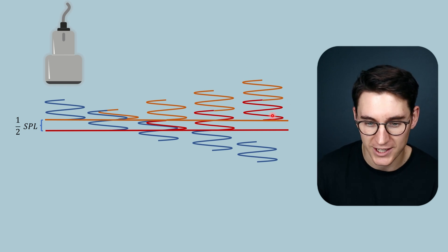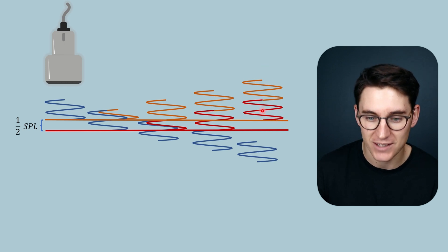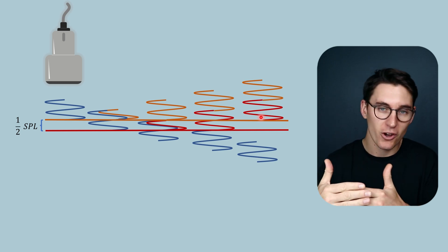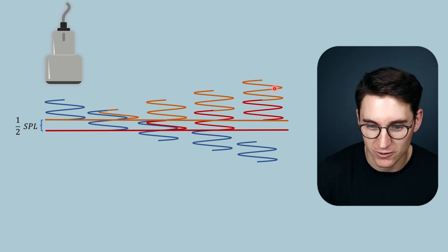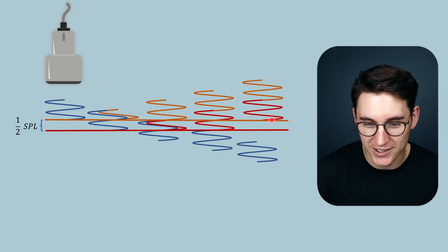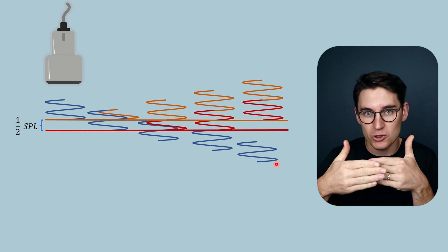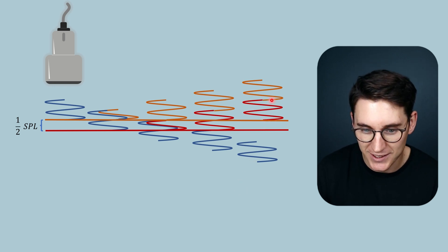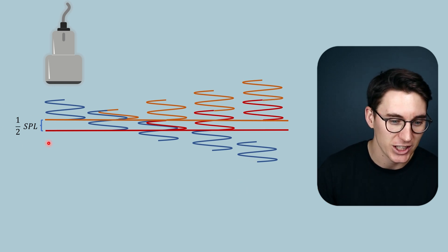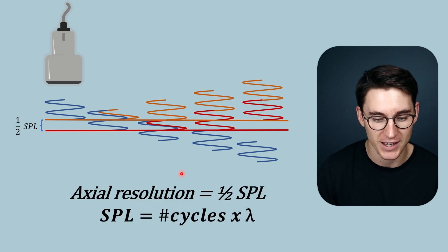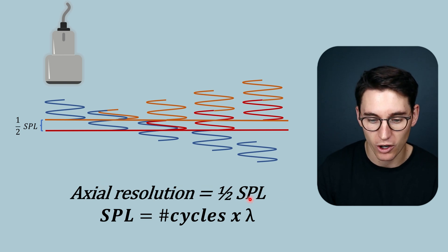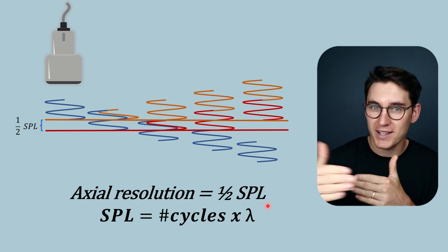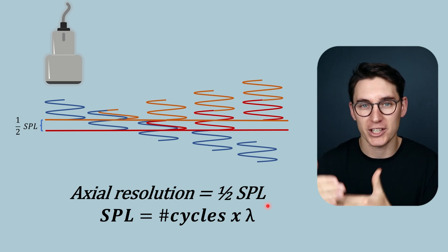There is no space between the first echo and the second echo. When this information heads back towards our ultrasound transducer, it will not be able to differentiate the first pulse echo from the second pulse echo, and it will plot this information as one solid line. The ultrasound machine is unable to resolve these two tissue boundaries because they are too close together. This shows us that the limit of axial resolution is half of the spatial pulse length: any two objects closer than half a spatial pulse length within the axial plane cannot be differentiated.